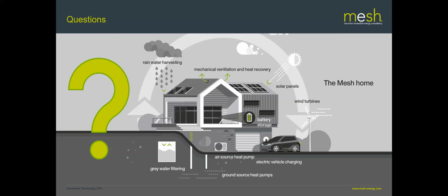I haven't seen a combined system, but I would assume that they'd have to have something. If you did have something like that, they would have to have something that deliberately directed the flows away from one another. And then you'd probably want to make sure it was in quite an exposed position so that you didn't get any kind of short circuiting. But yeah, short circuiting is the issue. You don't want to be mixing the intake air with the exhaust air.